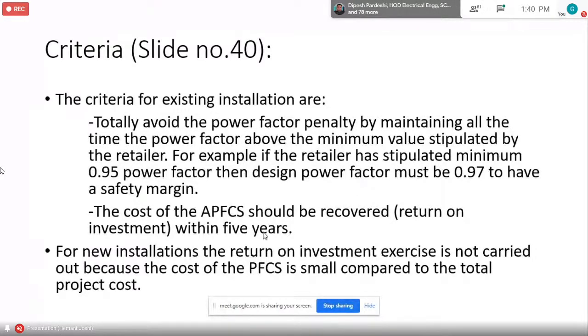Okay. The new installation, no need to worry about. For a new installation, the return on investment exercise is not carried out because the cost of the power factor correction is small compared to the total project cost. So when we are designing a new installation, we don't do this return on investment calculation. On existing, you may do it or you may not do it. It's the client's choice.